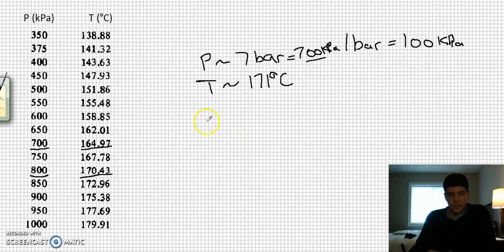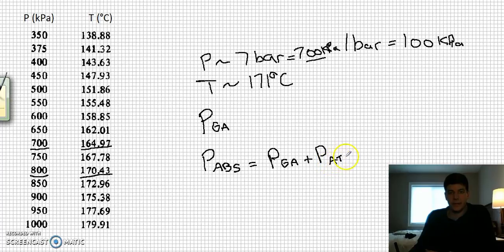Actually, what's happening is when we read off the pressure inside of the boiler, what we have is what's known as gauge pressure. Gauge pressure is what we would read off of the gauge. If the boiler had no pressure in it, it would show zero gauge pressure. What the tables are all arranged in is absolute pressure. Even though I don't feel any pressure on my body right now, I know that there's air pressure acting on me, atmospheric pressure. What I have is a relationship between gauge pressure and atmospheric pressure and absolute pressure: P_absolute equals P_gauge plus P_atmospheric.